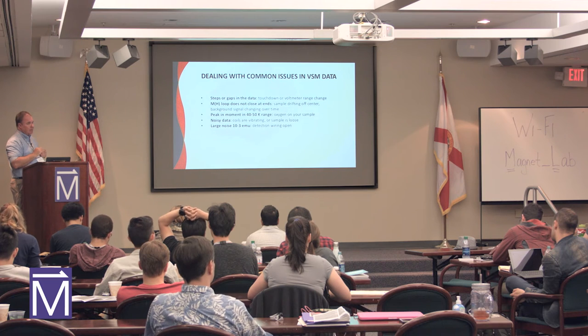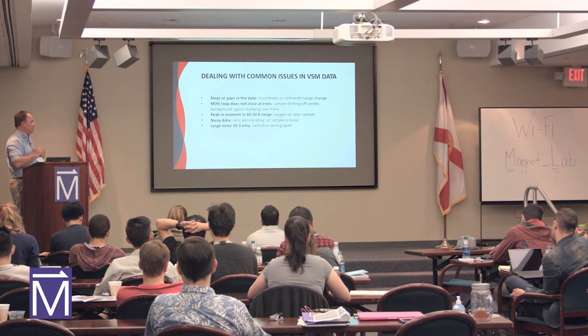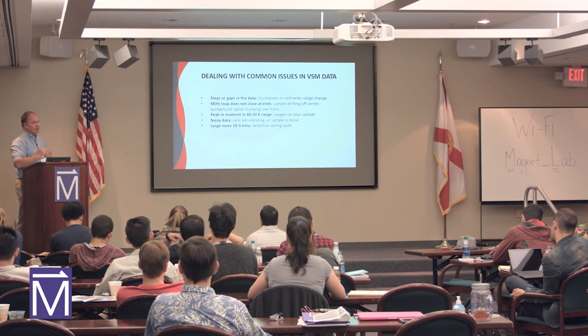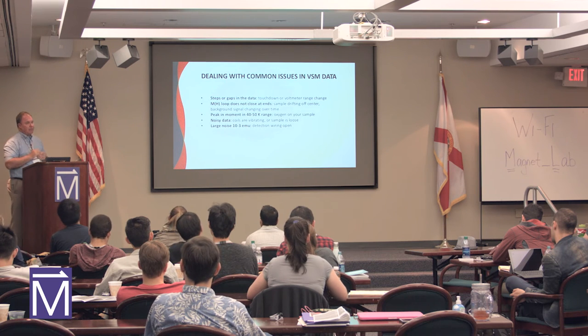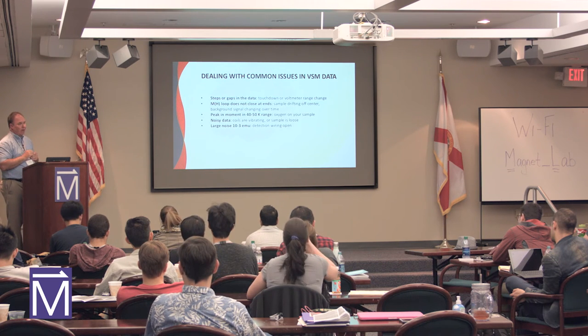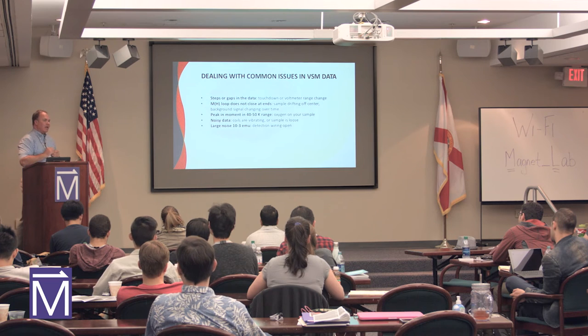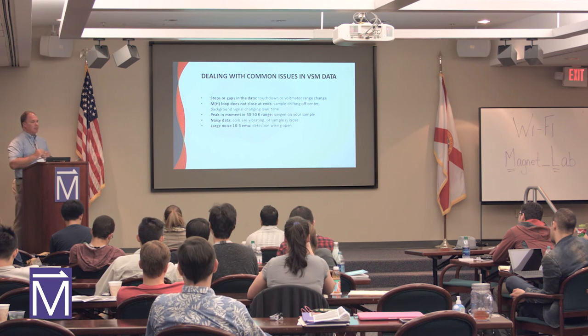Noisy data, sample's loose, the coils are vibrating, and if it's a large moment, then there's probably something wrong with the detection wiring. So look at how the connections are made on the system. And in those cases, you're typically going to call us.